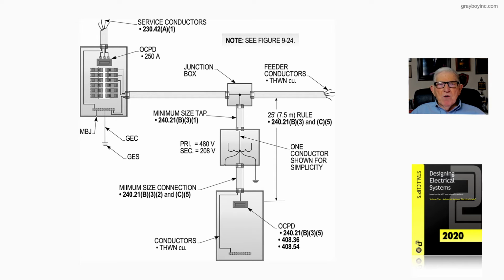So we're tapping from the feeder, and we're tapping off the secondary side of the transformer, and the total length from the tap from the feeder to where we terminate in the panel board, including the transformer, can be no more than 25 feet, as we are told in 240.21(B)(3) and (C)(5), which deals with B3 tapping from the feeder and C5 tapping from the transformer.